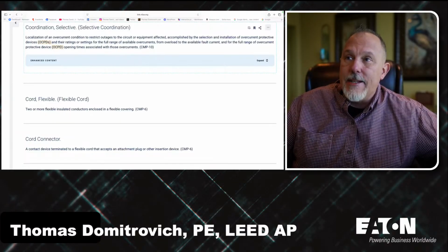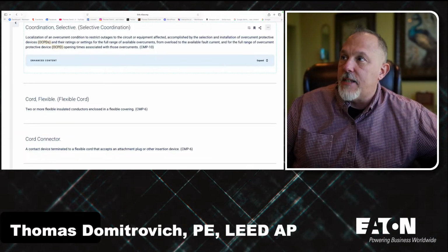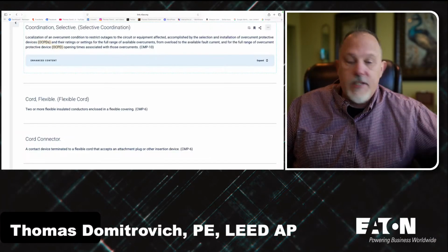Accomplished by the selection and installation of overcurrent protective devices and their ratings or settings. Let's stop right there. So we need to select overcurrent protective devices, whether they be circuit breakers or fuses or relays. These are overcurrent protective devices. Overcurrents, again, defined term. Ratings, meaning the long time pickup and things like that, interrupting ratings, all of that jazz.